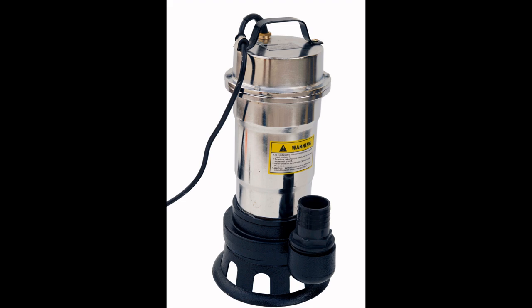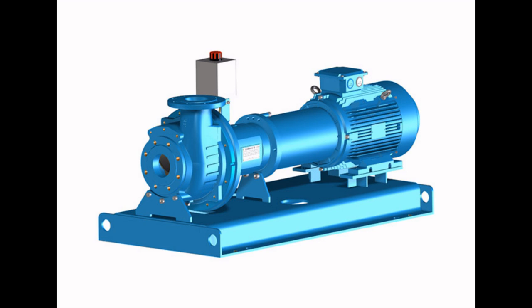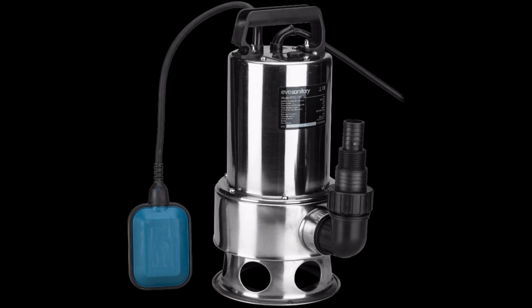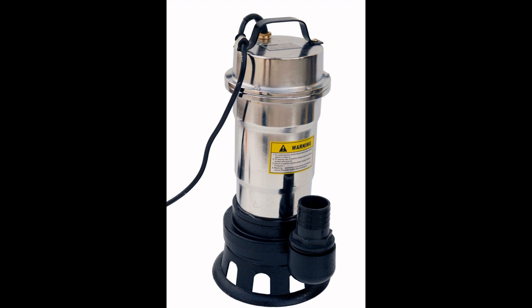6. Lifting, pumping height. The energy that the water obtains through pumping determines the height of the water, head or lift. For a surface pump, the lifting height of the pump includes suction and discharge, is marked with H and is measured in meters. For a submersible pump, H is only the discharge height. The vertical distance from the pump turbine to the surface of the water source, the height of the water column that the pump absorbs, is called the suction height. In short, suction. The vertical gap from the pump turbine to the consumer, the height of the water column that the pump discharges, is called discharge height. In short, discharge. The lifting height of the water pump equals suction height plus discharge height.